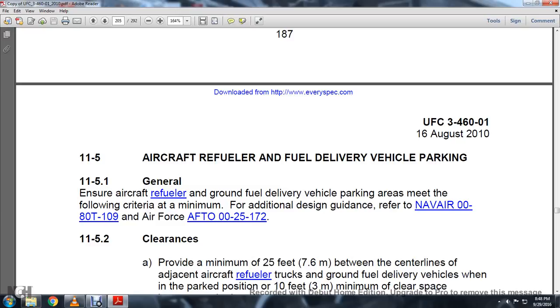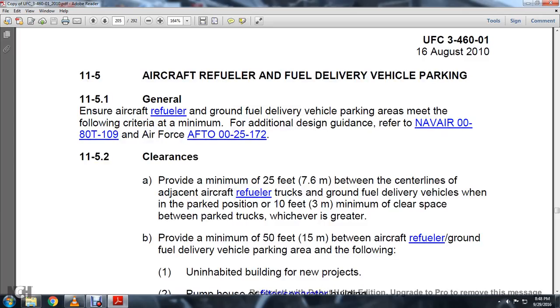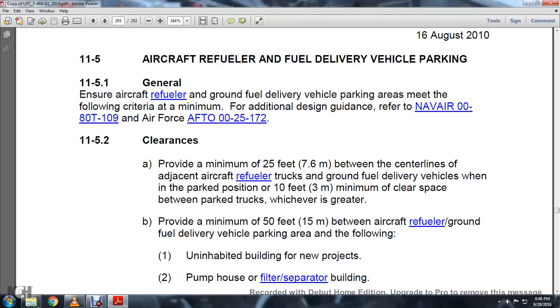11-5, Aircraft Refueler and Fuel Delivery Vehicle Parking. 11-5.1, ensure aircraft refueler and ground fuel delivery vehicle parking meet the following criteria. For additional design guidance, refer to NAVAIR 00-80T-109 and Air Force AFTO 00-25-172. Clearances: provide a minimum of 25 feet between the centerlines adjacent to the aircraft refueler or truck, the ground fuel delivery vehicles, and the parked position, with 10 feet minimum of clear space between parked trucks, whichever is greater.